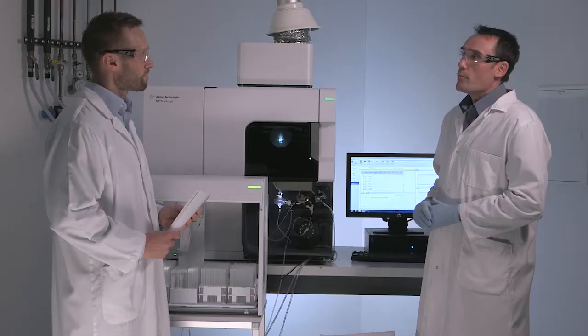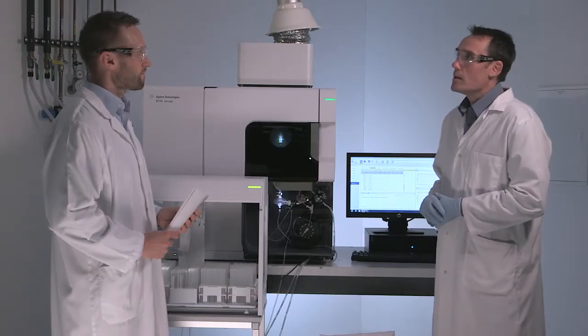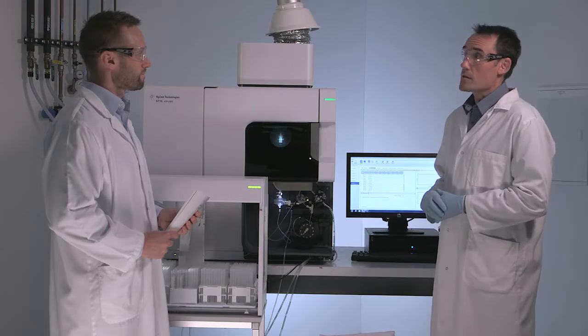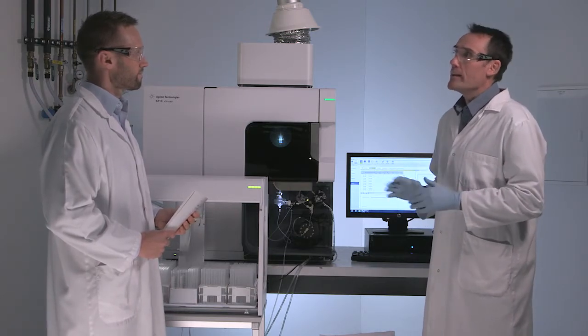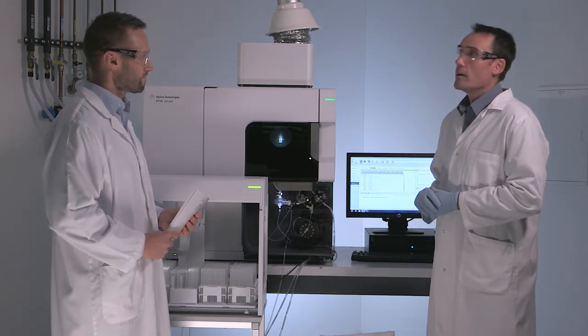Not all customers run thousands of samples per day. Does the Advanced Valve System also add value for those customers? The AVS technology, if it's not required for thousands of samples per day, will be ideal for fast turnaround of only a few samples. Not only that, the high throughput technology significantly reduces the wear and tear on common consumable components like the torch and the peristaltic pump tubing.